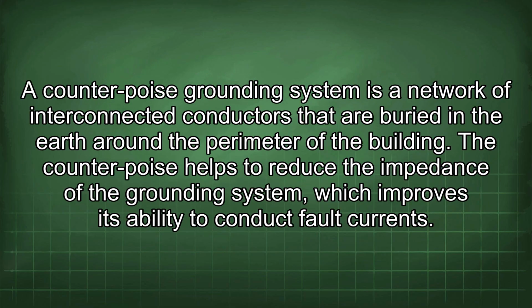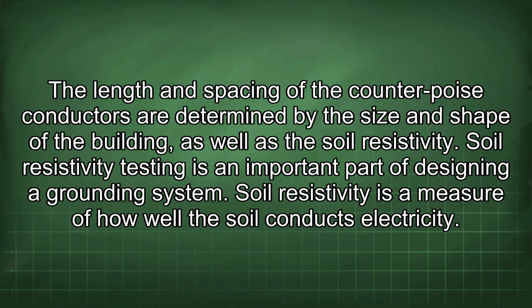A counter-poise grounding system is a network of interconnected conductors that are buried in the earth around the perimeter of the building. The counter-poise helps to reduce the impedance of the grounding system, which improves its ability to conduct fault currents. The length and spacing of the counter-poise conductors are determined by the size and shape of the building, as well as the soil resistivity.